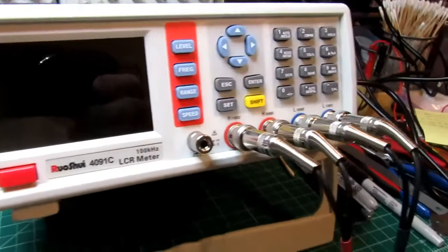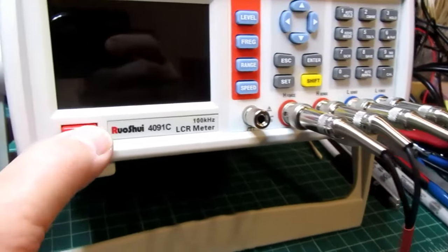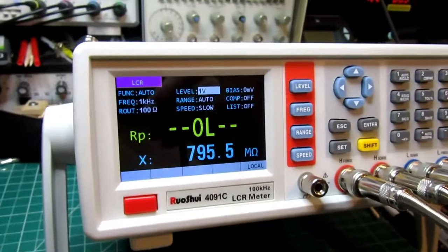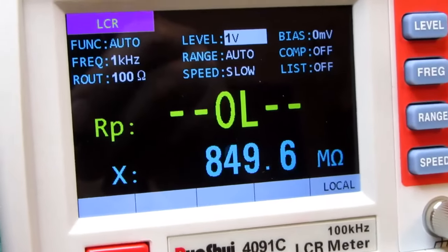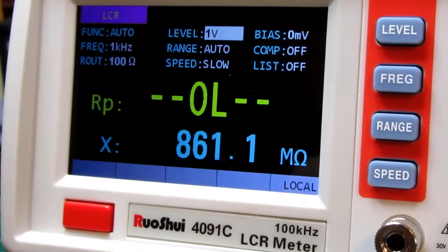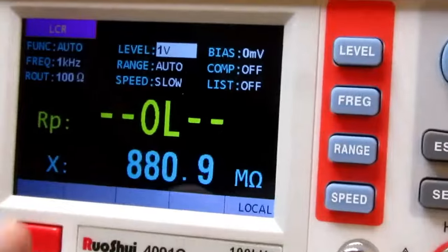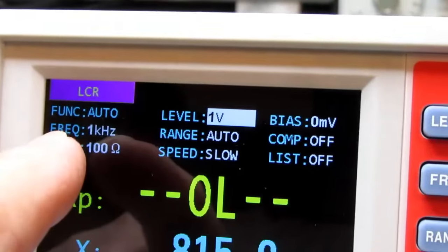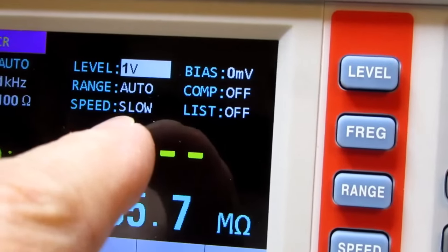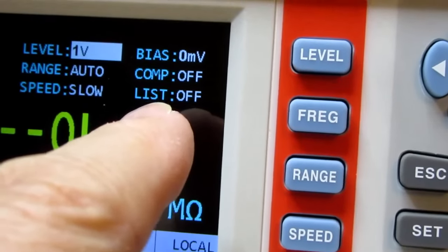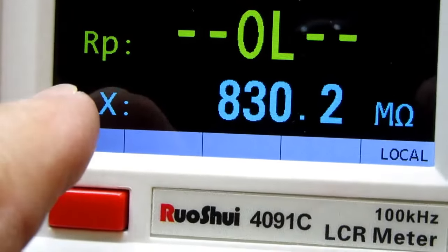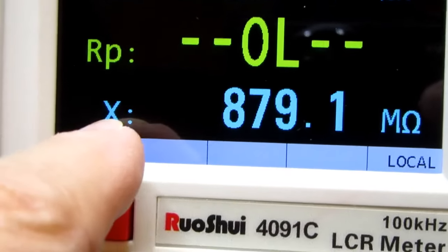I have all the test lead connectors plugged in. Push the power button. Looks like a pretty clear display. I'll view it from this angle, less glare. So this is a bunch of settings here. The function is in auto. Frequency is set to 1 kHz. R out is 100 ohms. Level is 1 volt. Range is auto. Speed is slow. Bias is 0 millivolts. Compensation off. List off. This will be your primary parameter. Currently it's set up for resistance parallel and reactance.